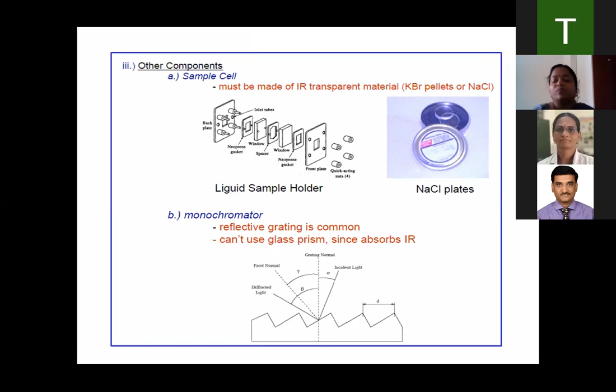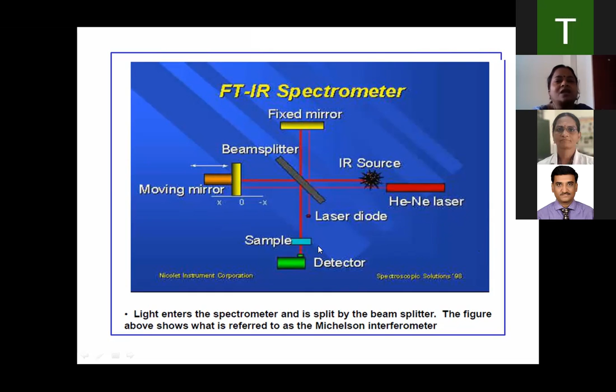And this is again the same picture, the Michelson interferometer, so you can get a wide picture of that. A laser diode is there. You have a fixed mirror, a moving mirror, a beam splitter, everything: the IR source, and then the detector and sample. You can see here the sample is placed almost near the detector. And this IR source is again provided with a helium-neon laser in order to have good, continuous calibration.